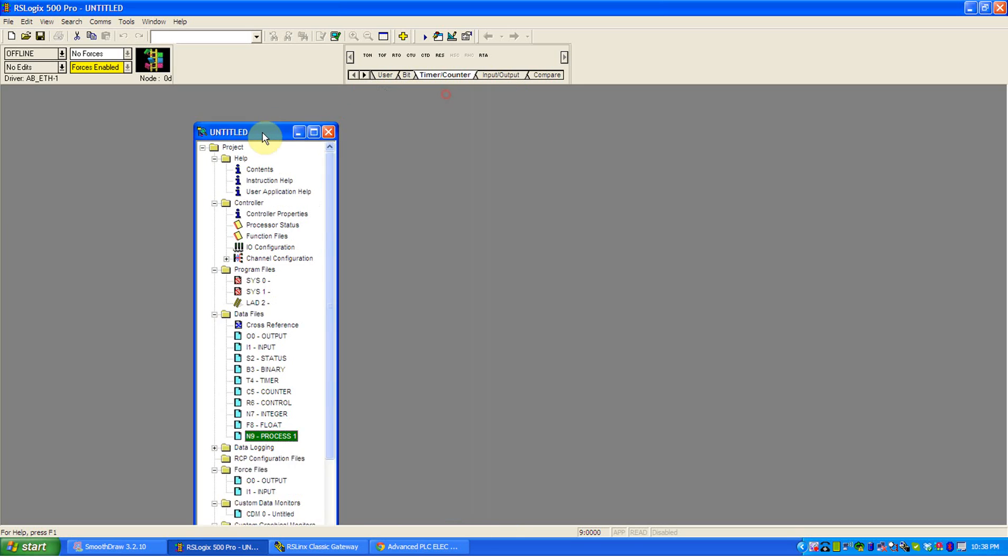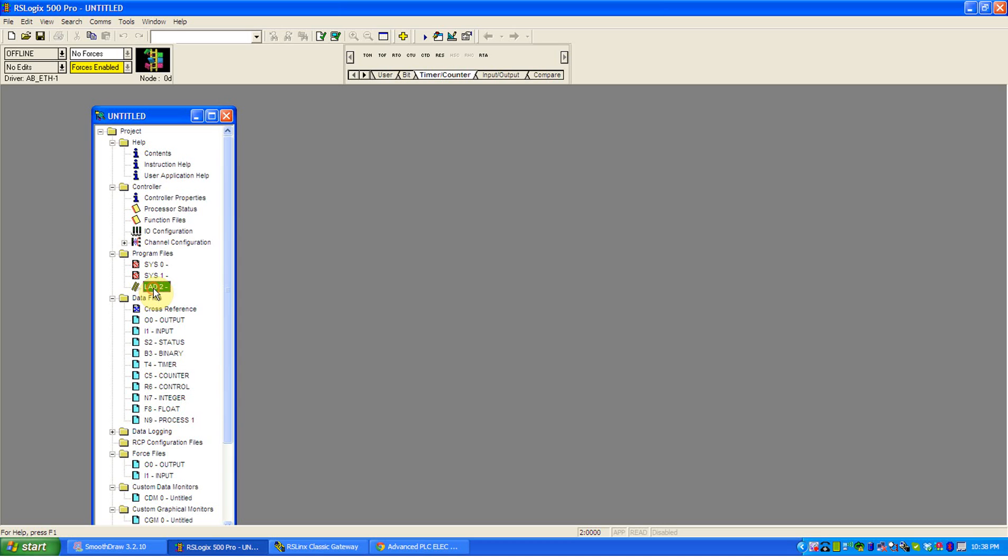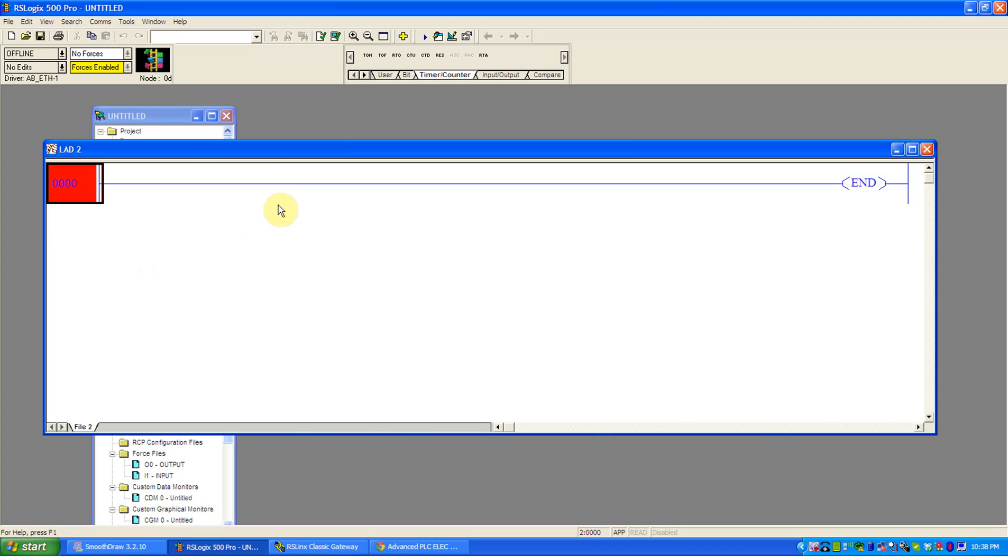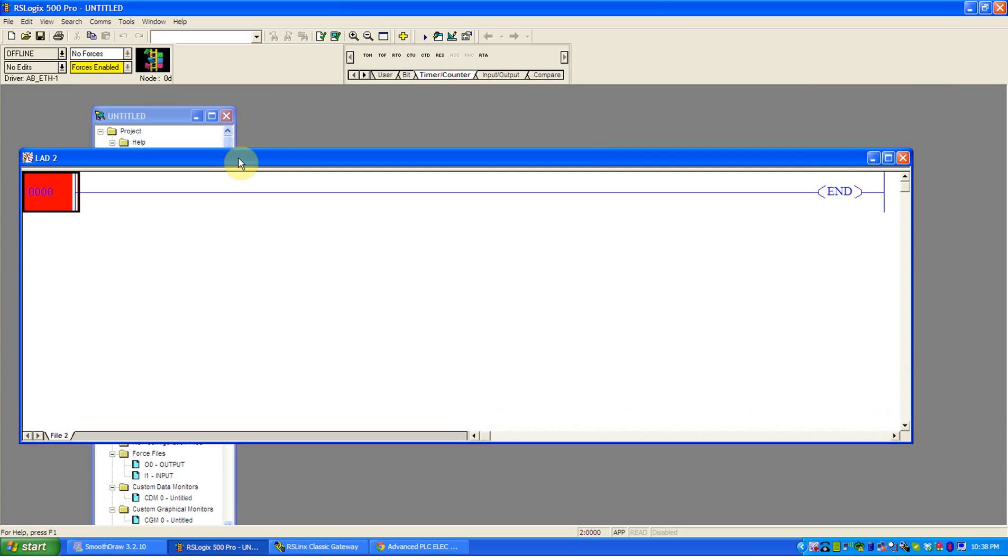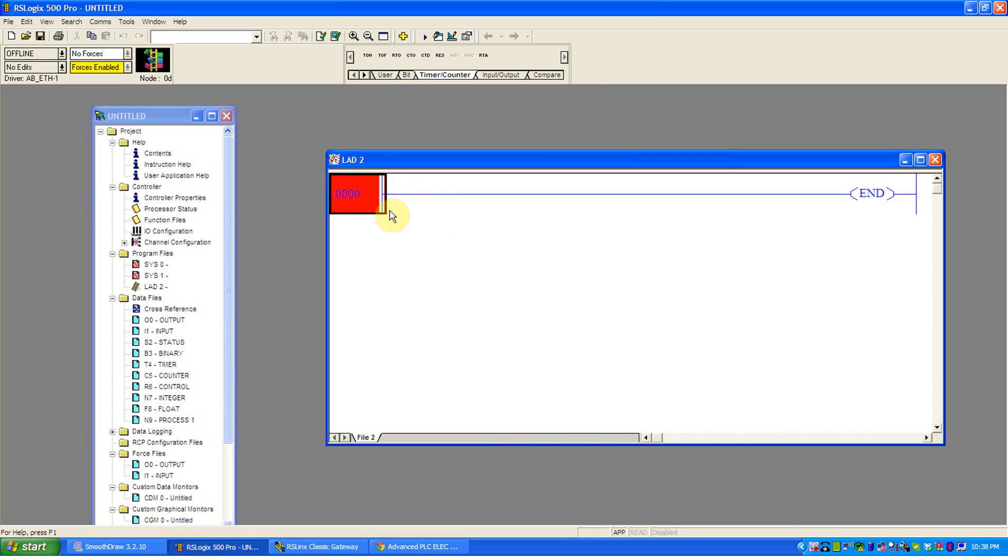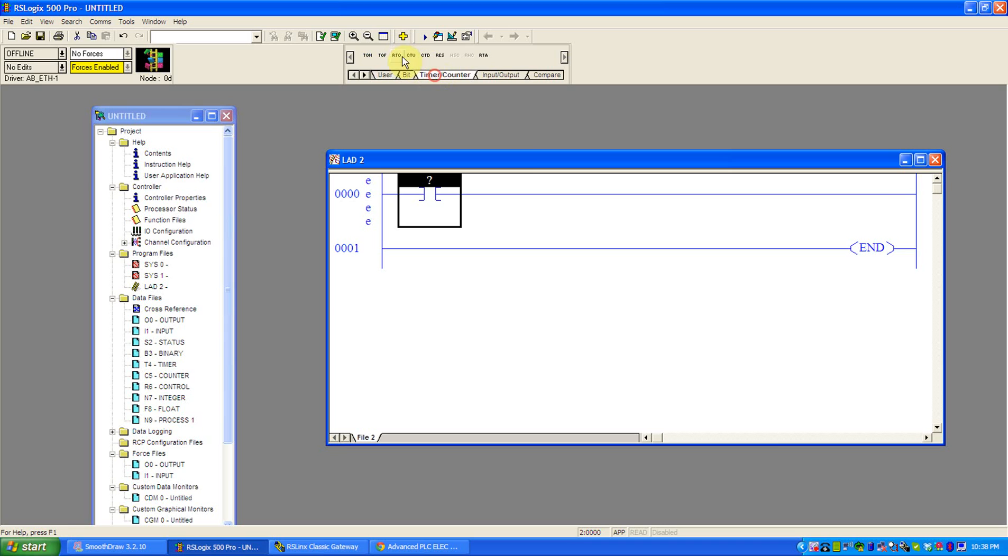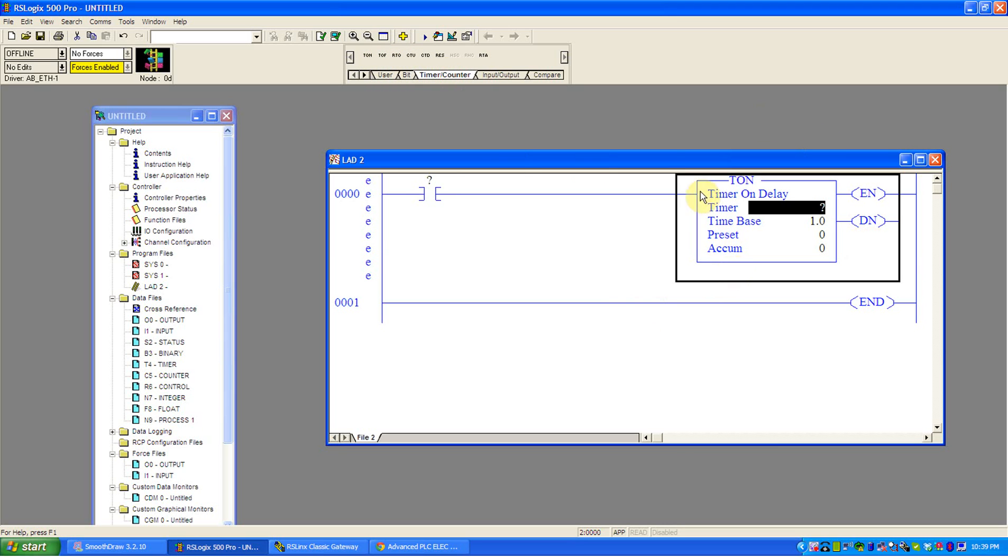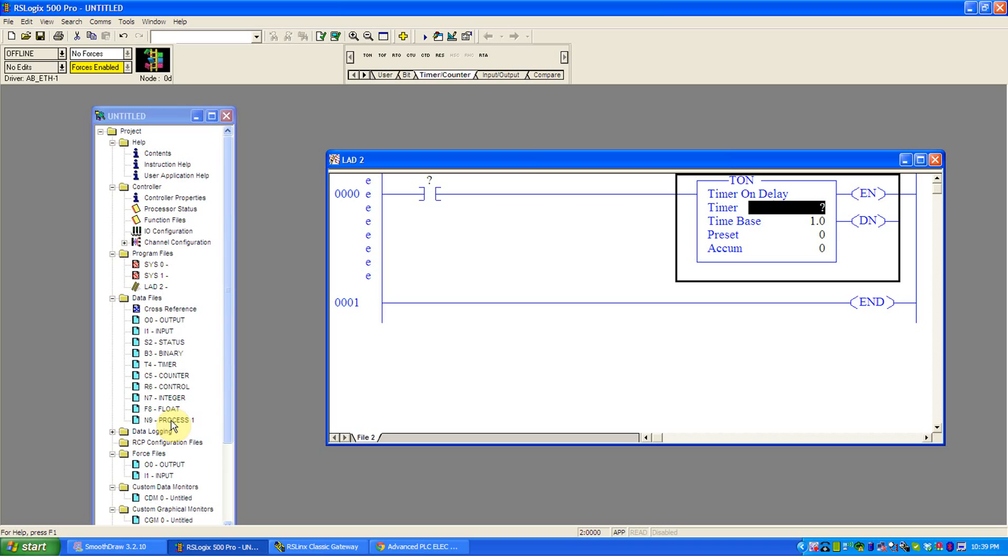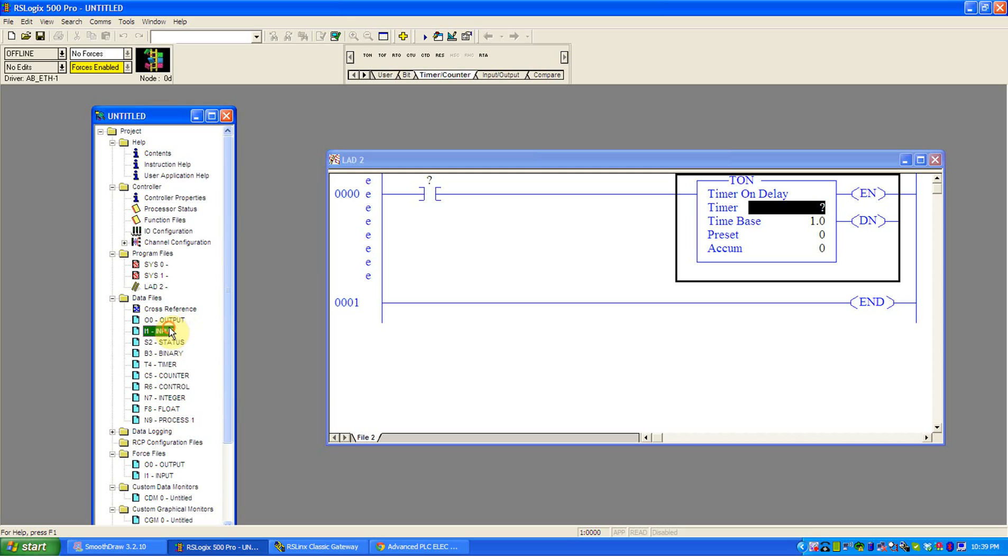It's all just memory. When I open up PLC logic, like this file, which is just a single file in the folder called program files, what I get is a graphical representation of it that looks like ladder logic. And I can add contacts and timers and all sorts of things in here. And all I'm really doing here is just referencing this information, these data files over here, I want you to make decisions. So if the data file for say input is on, do the timing function for this data file. But I'm really just writing logic to make decisions and manipulate this. Of course, inputs and outputs reference the real world. The rest of this is just internal stuff that we use to help make these decisions.